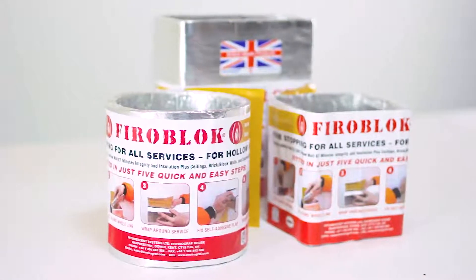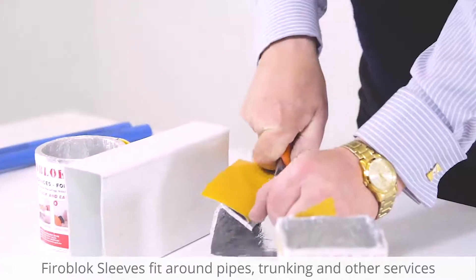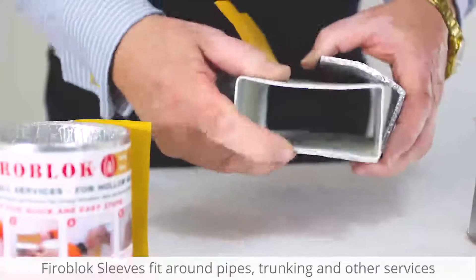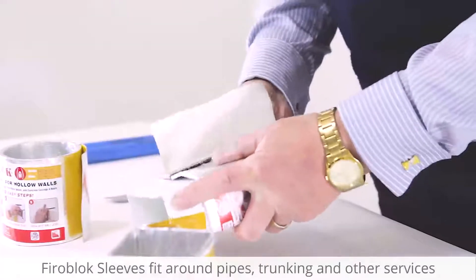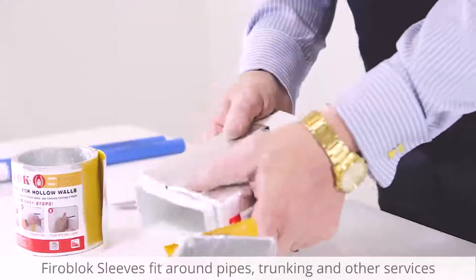Next up is our Firoblok Intumescent Sleeve in action. The Firoblok is easily installed and is designed to be retrofitted if needed. Simply cut through the back of the sleeve and place around the trunking. A self-adhesive tag is then peeled back in order to rejoin the cut. The finished product is then simply placed into the wall flush on each side.